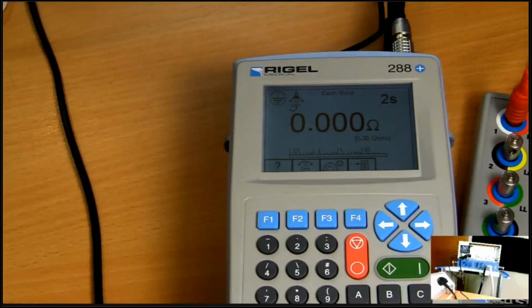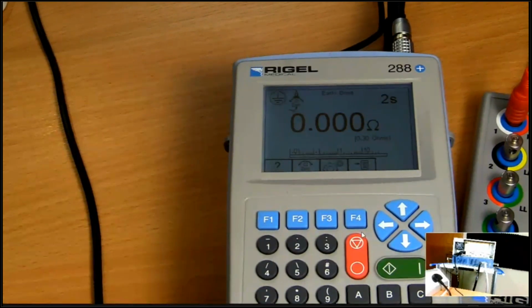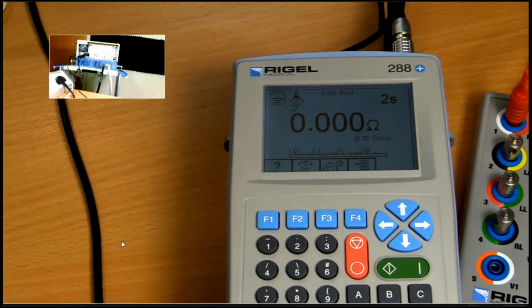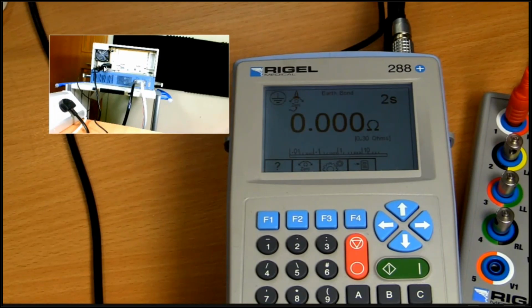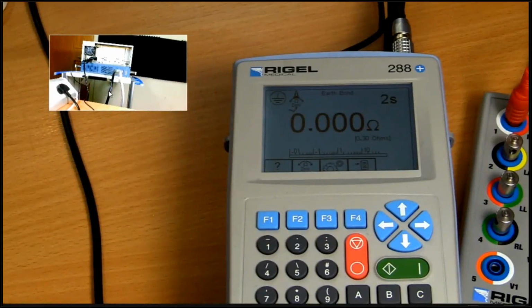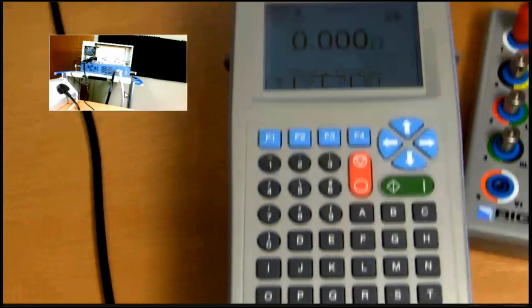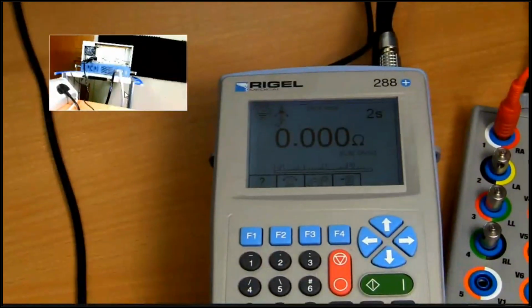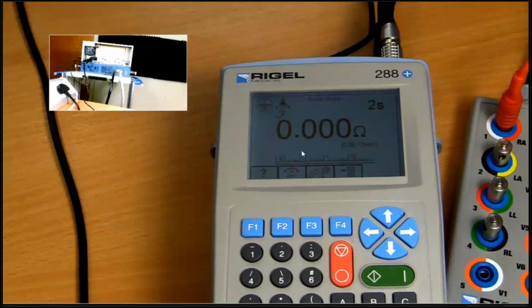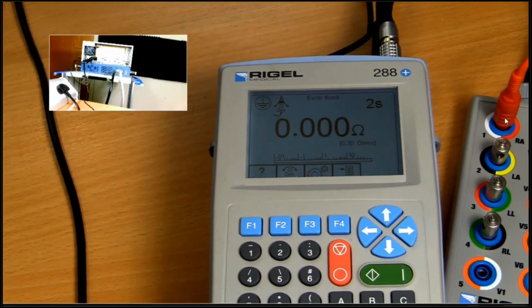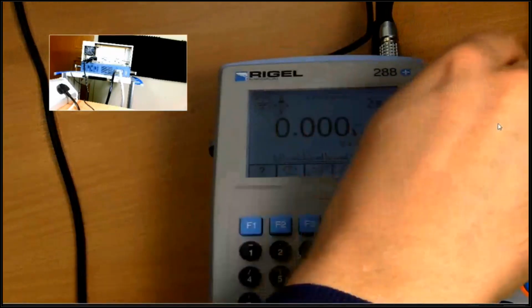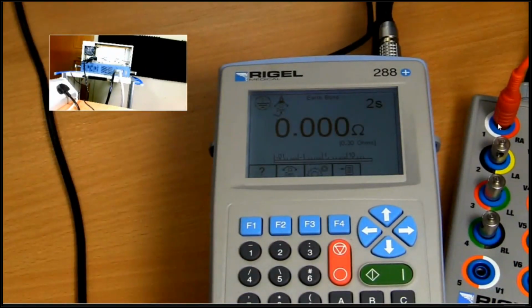Right, this is our 288. And over here is our medical device, which happens to be a ventilator. It's 1BF, so I'm going to set this up as a 1BF. I've got my alligator or crocodile clip going to an exposed metalwork, so I've already preset this up. And then I have the device under test plugged into my safety analyzer. I have the applied parts here, connected to my applied part 1. And I'm going to set this up to do an automatic test.